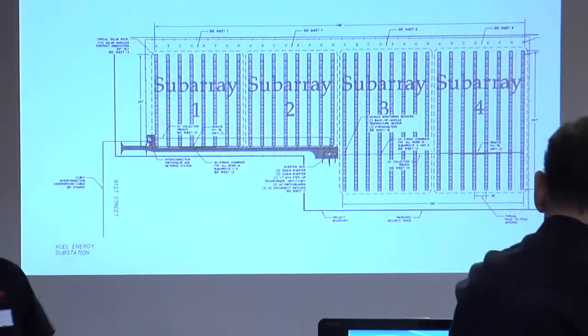How many modules per string? I believe it was 11. Is it 600 volts? It's a 600 volt system. Bipolar system. Correct. Is it bipolar with the full neutral, or is it bipolar with the reduced? It's full. So your common's coming back out pretty big wires. Right. Yeah, the common is correct.